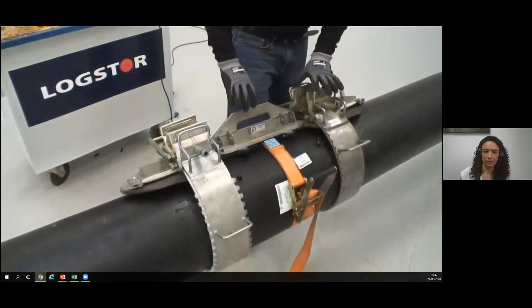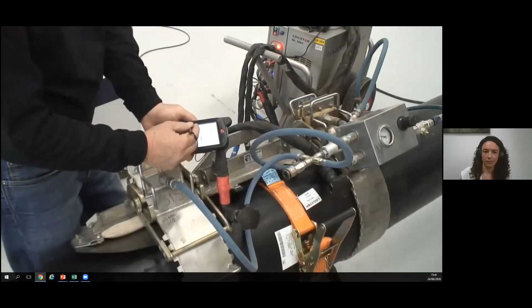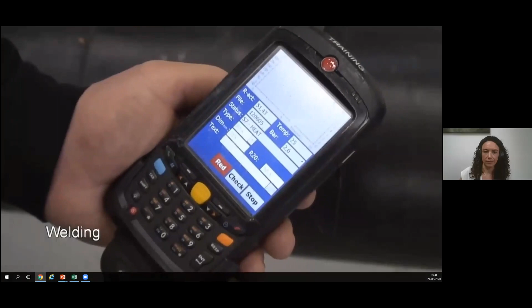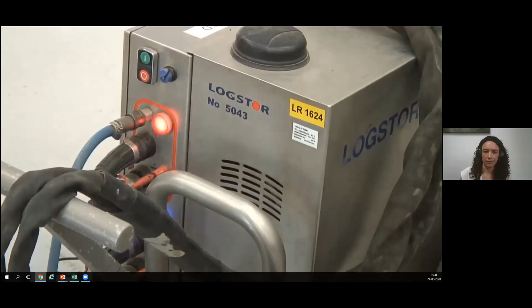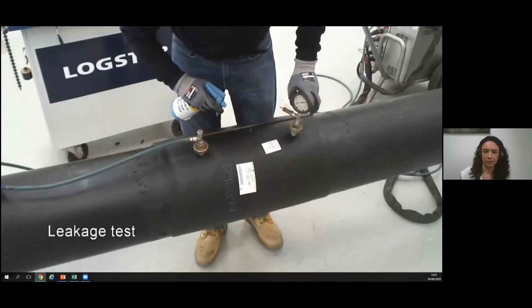So that's the casing going on, being tightened up, the clamps being positioned. This is the old style of branch, which will be phased out, and we're going to a much simpler one currently. So that's the Weldmaster being all plugged in. We've got the PDA there. You'll scan that with the barcode, which then puts all the correct temperatures and pressures into the Weldmaster. Turn on the Weldmaster, it'll go through its sequence. That will generate a yes, no, it's gone okay or it's not okay. And that will also then provide you documentation up into our server.